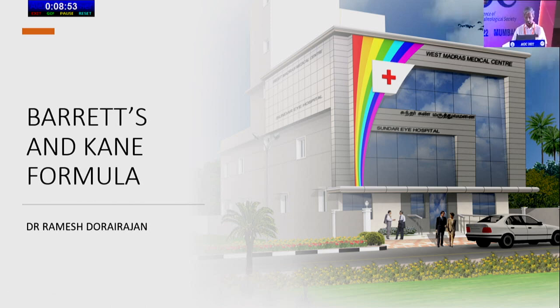Thank you. So regarding the true K, it measures the front and the back, and then it calculates the actual true K of the cornea. It is found to be most useful in patients where you have a dissonance between the front and the back, like in ectatic eyes, thin corneas, keratoconus and post-LASIK eyes. For the normal, regular eye, the standard anterior K is still fine.